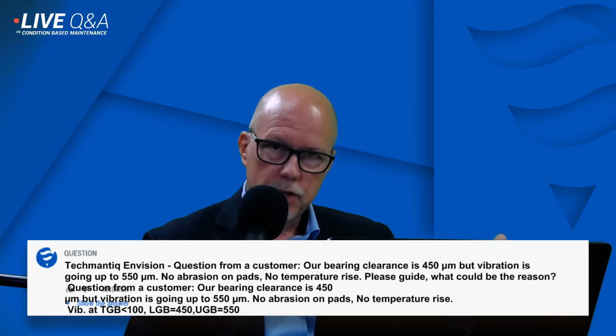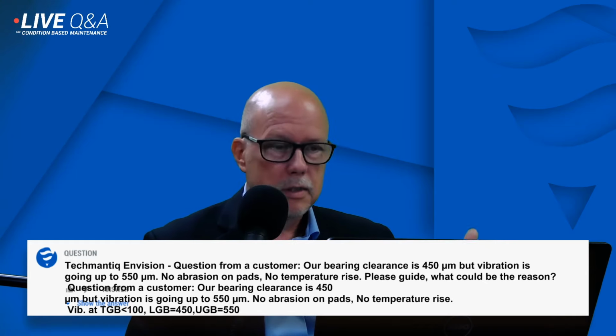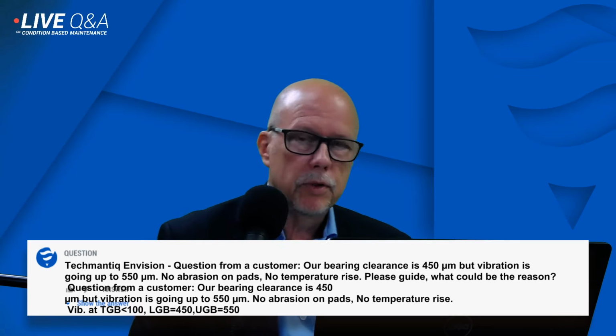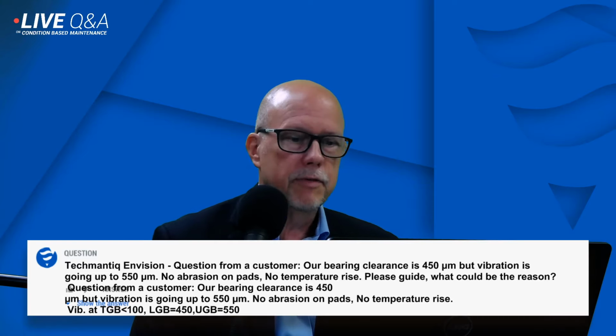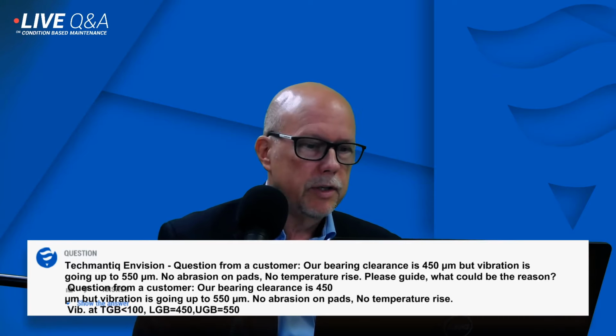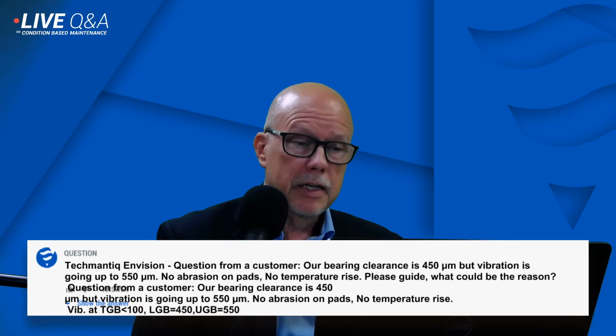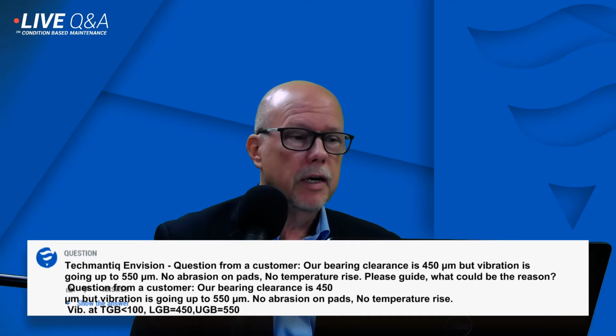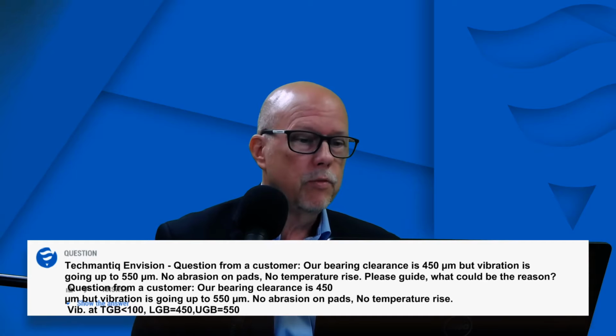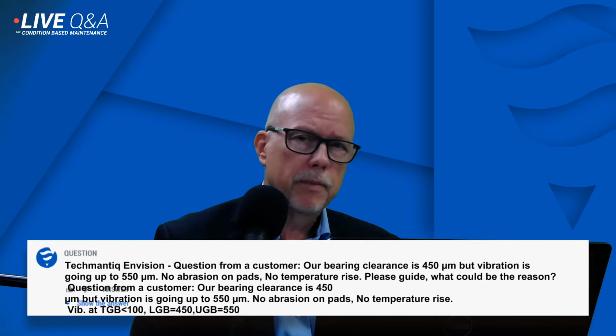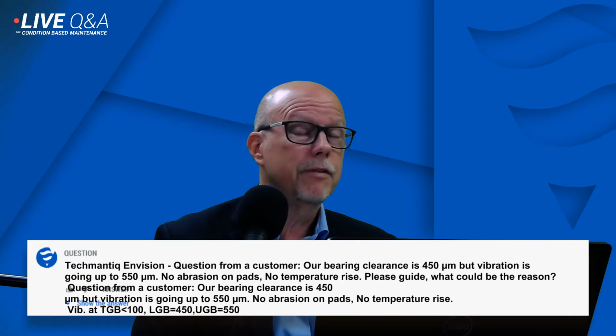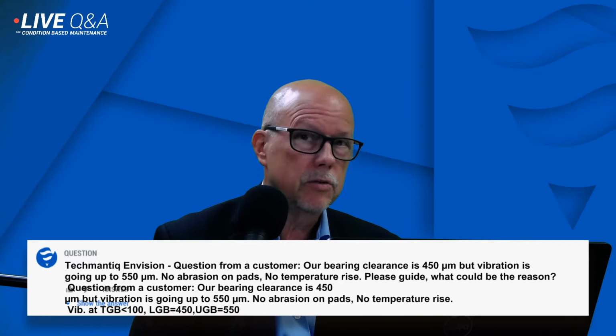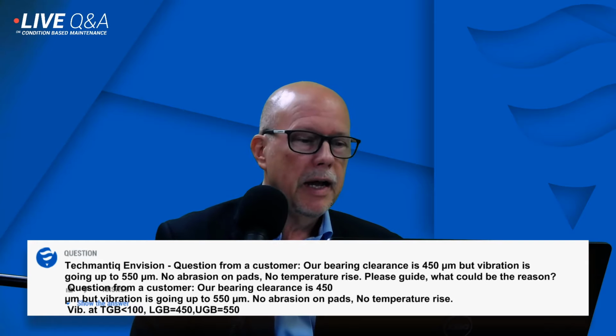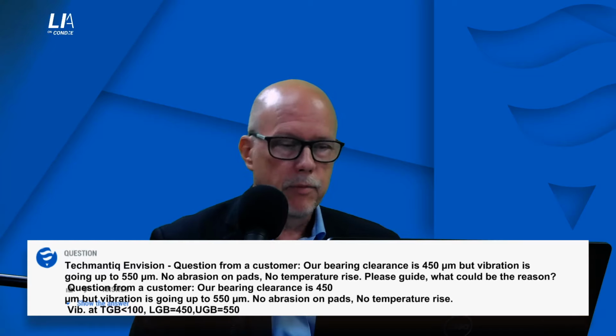So first and foremost, check what the gap is, what the clearance is. Second, check the calibration of your sensor. And then third, you might want to think to put some accelerometers on the bearing housing and see if that actually is contributing to the vibration. In this case also, the vibration was very high on top of the rotor. So you might want to install accelerometers on the upper bracket, especially if the upper bracket is only fastened to the frame. It's not fastened to the concrete housing of the unit. You might have a situation where there's tremendous amount of vibration there.